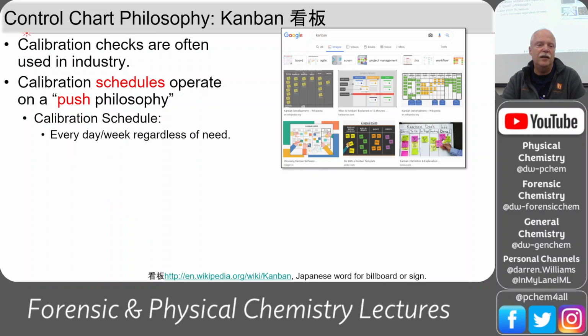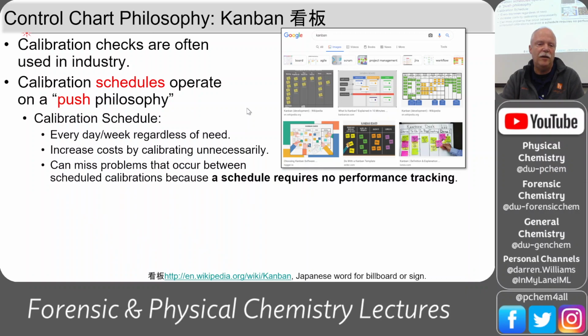So this is a calibration schedule, might be every day, every week, regardless of need. It's not based on the data, it's based on the calendar. So that's what we mean by calendar-based schedules or push philosophy. It's not based on the data.